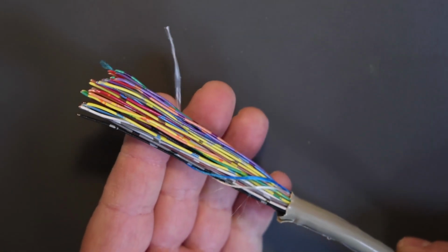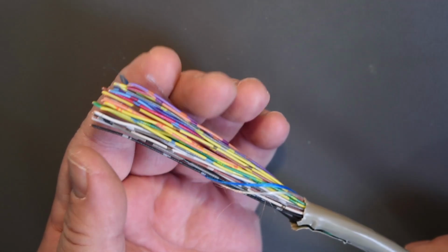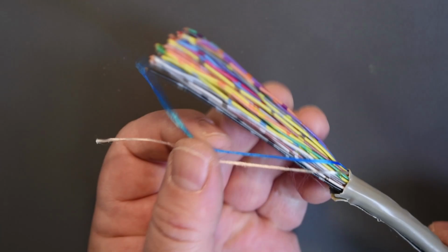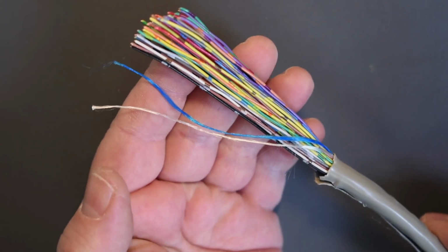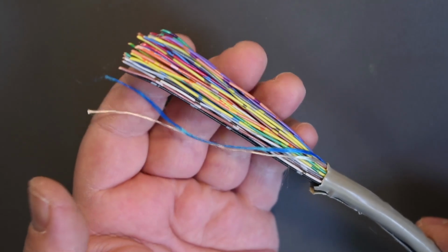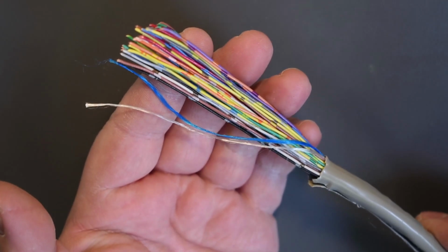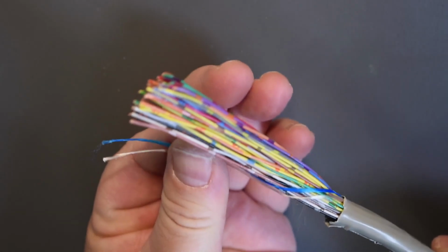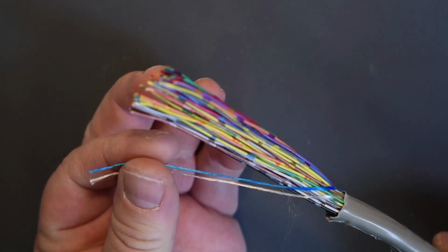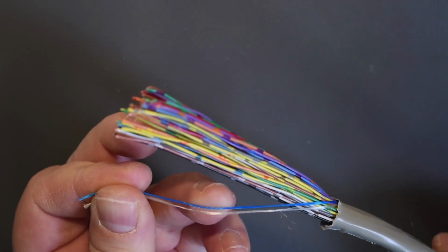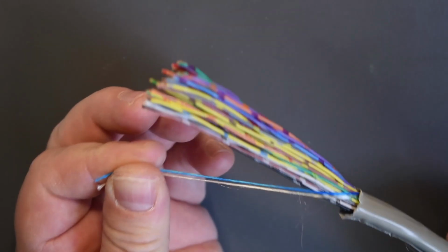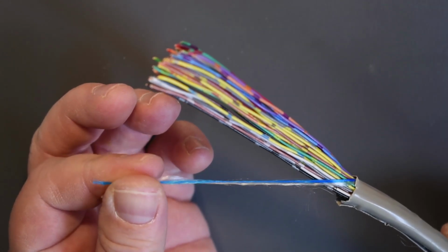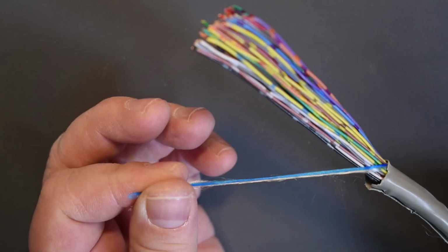Now, here's the idea of this. They bind these cables together. Also, the purpose of this blue ribbon spirally wrapped around is to mark the first 25 pairs. Because sometimes you're going to deal with something like a 100 pair cable, and 100 pair cable is 1, 2, 3, 4 of these in one jacketing, and they're separated by the spiral ribbons. So the first 25 pairs is going to be marked with the blue ribbon. Second one is going to be marked with the orange ribbon. And there's going to be a green ribbon and brown. So you can keep the bundles together.